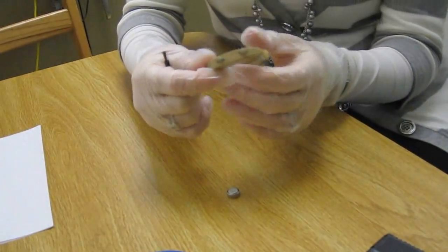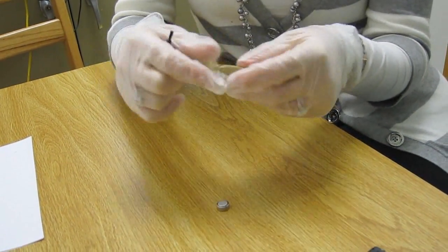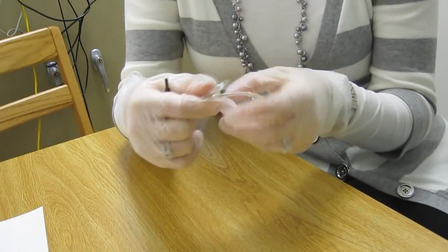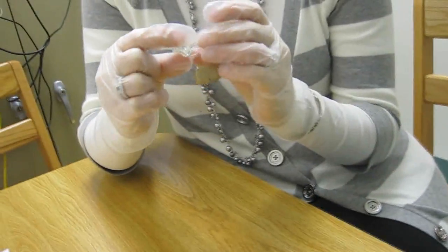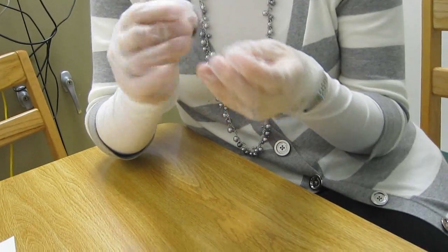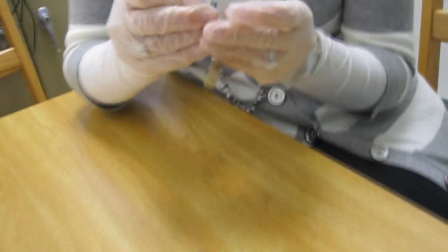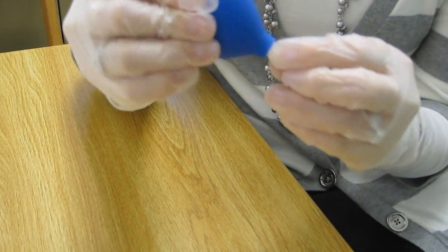Hi, it's Roxana Panis. We're going to do a visual inspection of the behind the ear hearing aid. So first we'll look at the casing to see if any cracks or breaks in it, but it looks good. There aren't any. So we look at the ear mold to see if there are any cracks or breaks, and it looks good. So we check the sound bore to see if there's any debris or wax. And there isn't, but we just cleaned it out just to make sure. Then we're going to check if there's any condensation in the tubing. Doesn't look like there is, but we'll just make sure there isn't. This gets rid of it if there is.